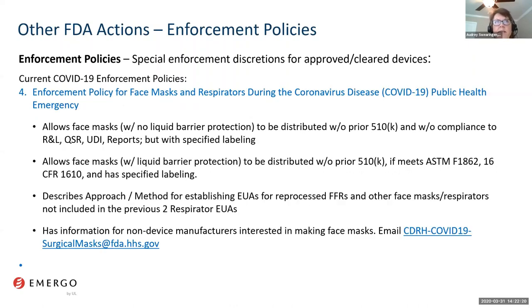There's an enforcement policy for face masks. It covers face masks with and without a liquid barrier protection with various types of requirements and criteria. With regard to those with no liquid barrier protection, you can distribute those without prior 510(k) clearance and also without complying with the registration and listing requirements, the quality system regulation, unique device identification, and medical device reporting. However, you do have to provide it with the specified labeling. And for those with a liquid barrier protection, they must meet this ASTM standard and Code of Federal Regulations Part 1610 requirements. And I've provided an email address here that the FDA provides for non-device manufacturers who are interested in making face masks to inquire of the FDA and engage them in discussion. Next, please.